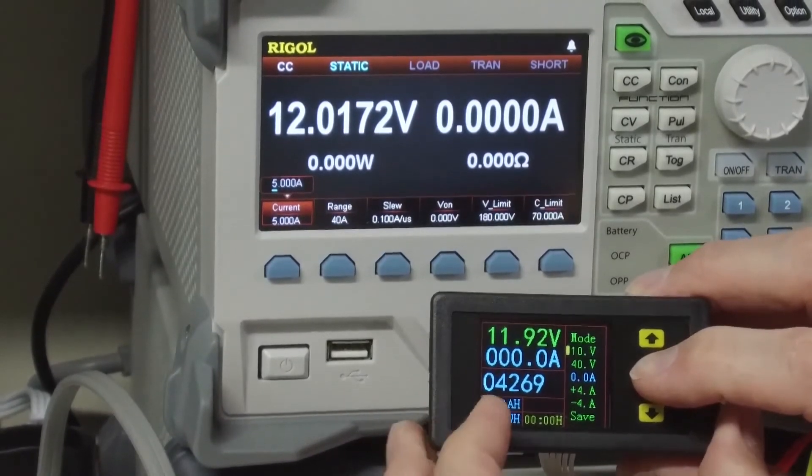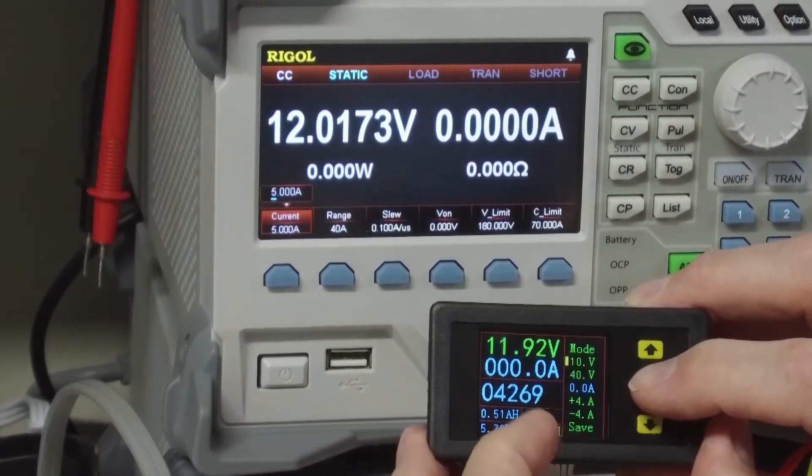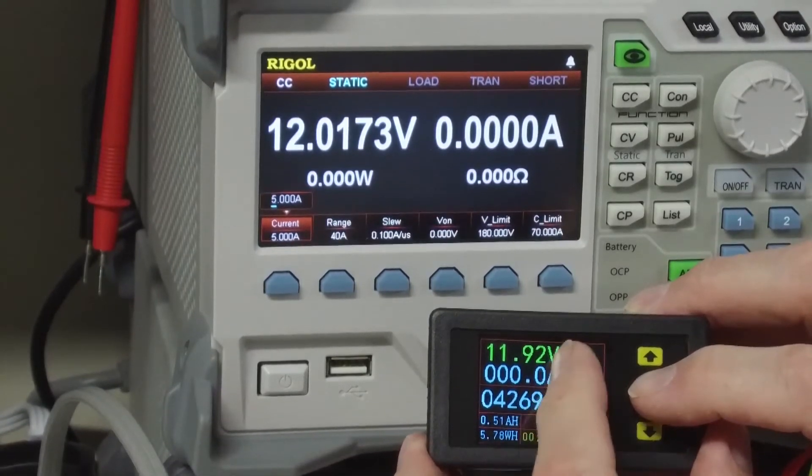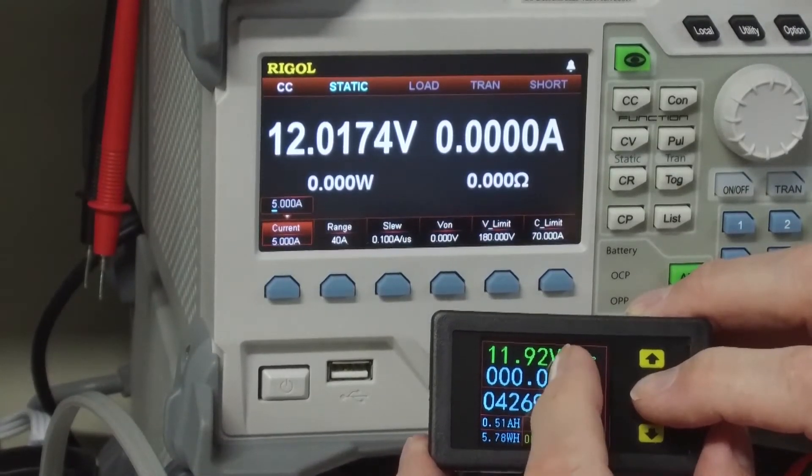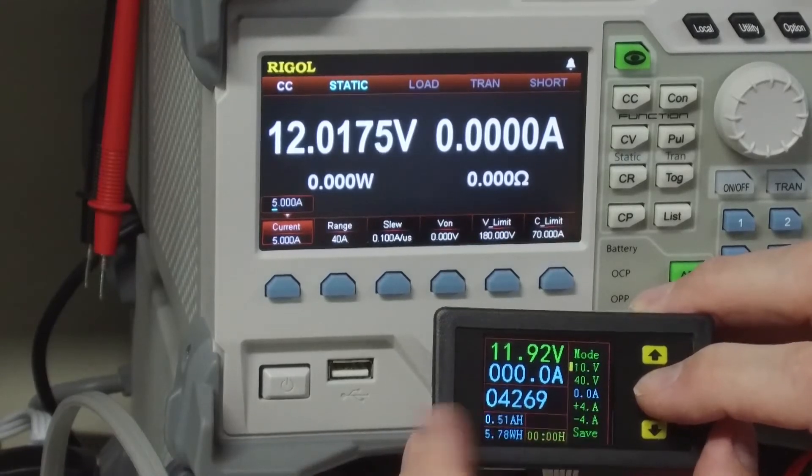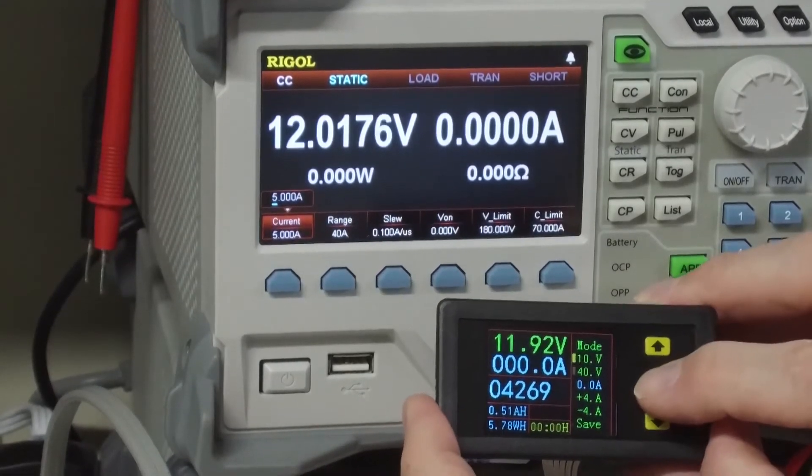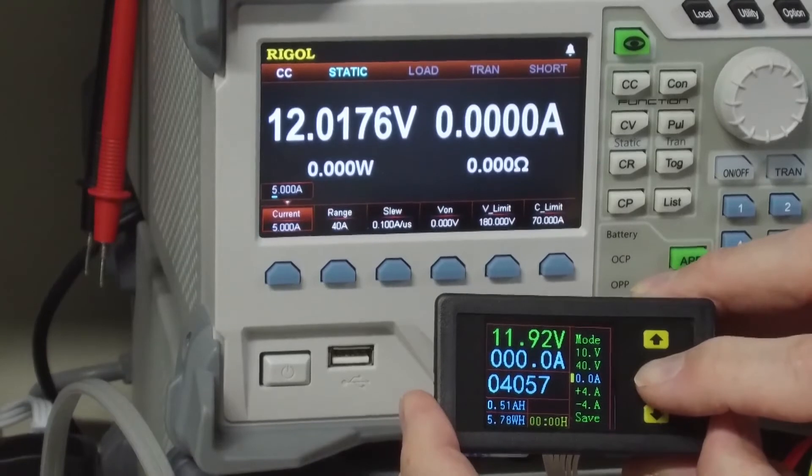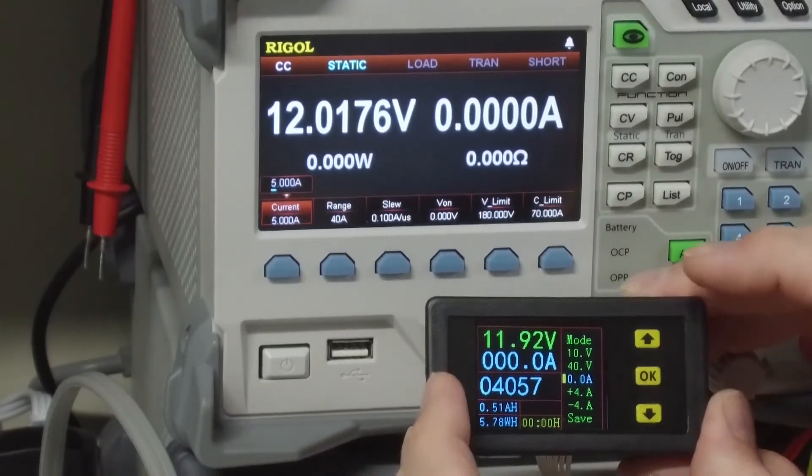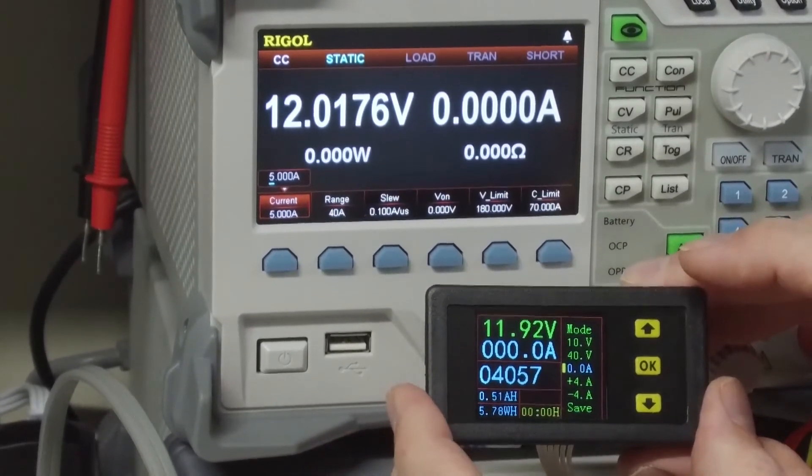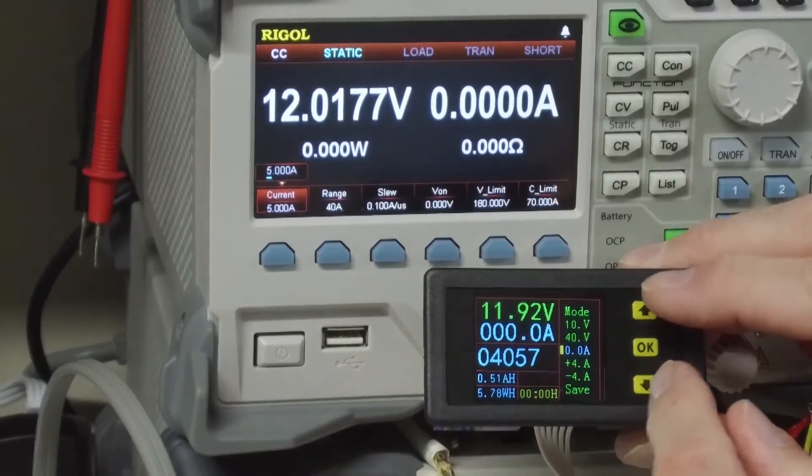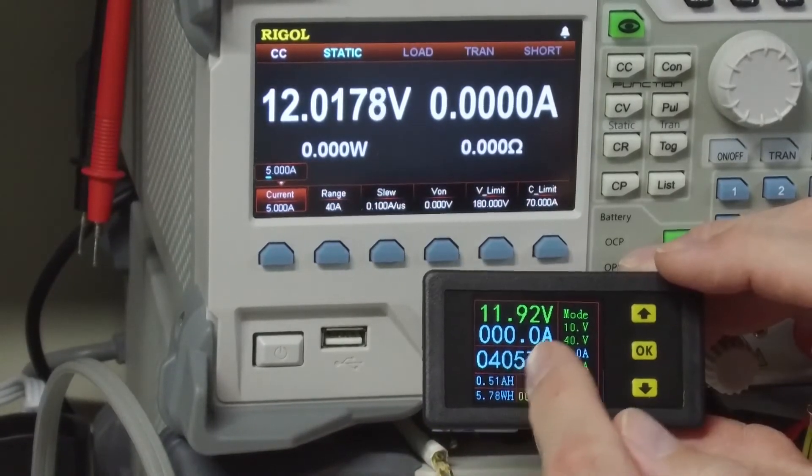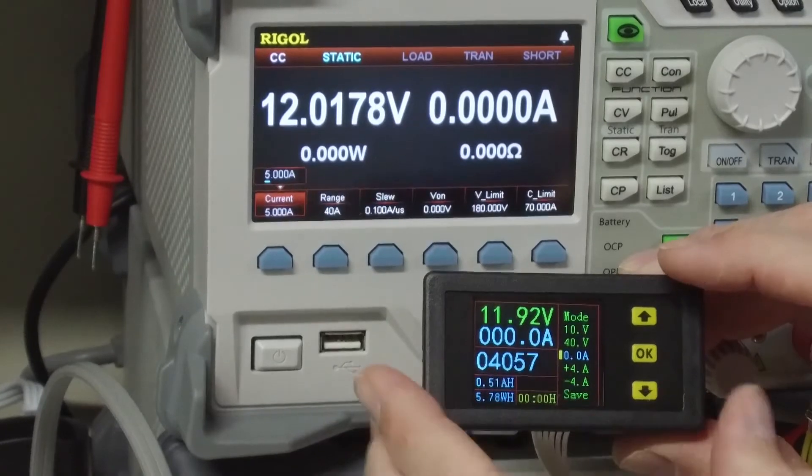This is, from what I can understand, this is a two-point calibration. And so you would do a calibration at a lower voltage and a calibration at a higher voltage. We're going to go to this zero amps. If this was displaying current while there is no current flowing, you would push the up-down button here to adjust the reading.